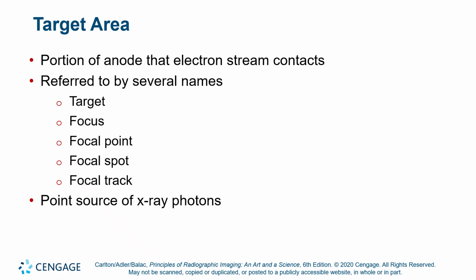The target area is the theoretical area where the electrons are actually intended to intersect the anode target. It's usually referred to as the focal spot. Occasionally it's referred to as the target, but that gets too generalized, and some people misunderstand. When you say anode target, they think you mean the entire anode rather than just the focal spot. So best practice is, if you mean focal spot, say focal spot. If you mean focal track, say focal track. If you mean the entire anode wheel, say anode. And that should eliminate the confusion.